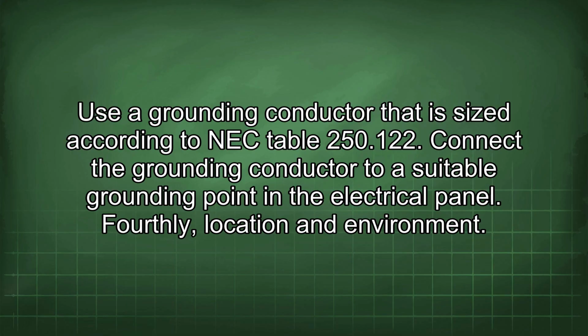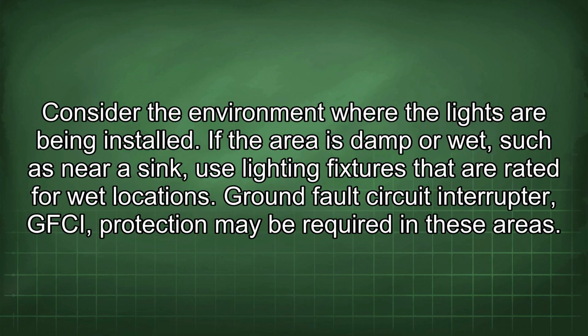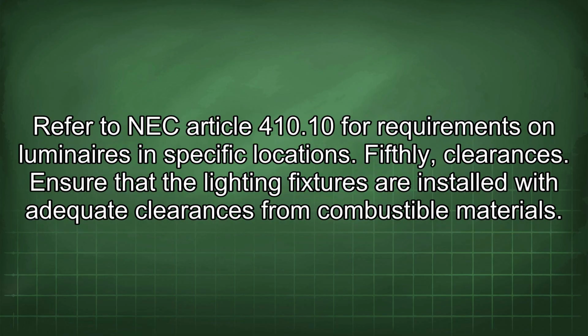Fourthly, location and environment. Consider the environment where the lights are being installed. If the area is damp or wet, such as near a sink, use lighting fixtures that are rated for wet locations. Ground fault circuit interrupter (GFCI) protection may be required in these areas. Refer to NEC Article 410.10 for requirements on luminaires in specific locations.